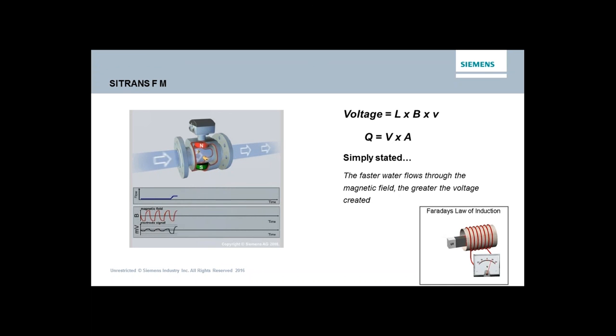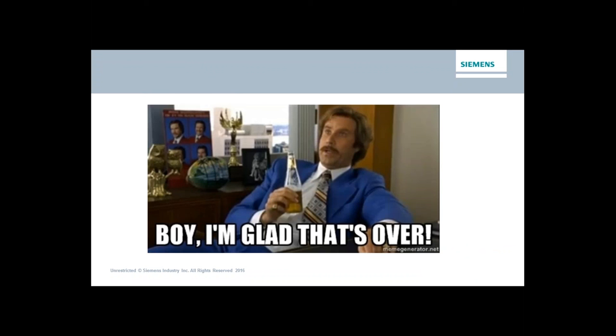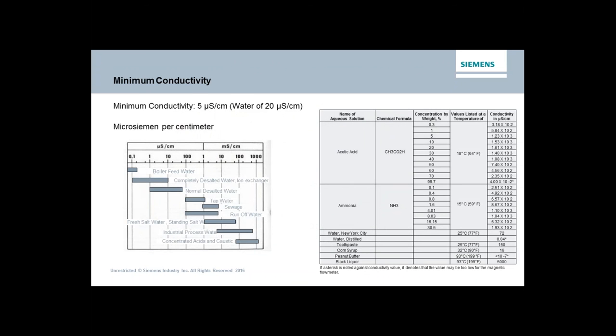If you look at your typical application — since we're dealing with water and wastewater here — tap water has a conductivity of 80 microsiemens per centimeter, and we need a minimum of 5. On the wastewater side, the materials in wastewater actually raise the conductivity up to where you'll get readings upwards of 100 to even 1,000 microsiemens per centimeter. For the applications we're dealing with specifically here today, we're not going to be concerned with conductivity because anything water-based used in a water or wastewater treatment facility is going to work just fine with a mag meter.